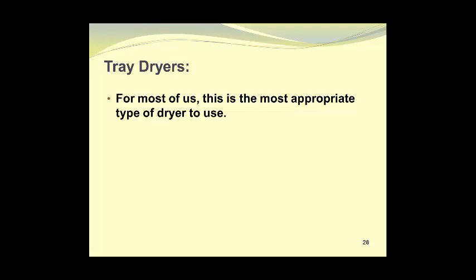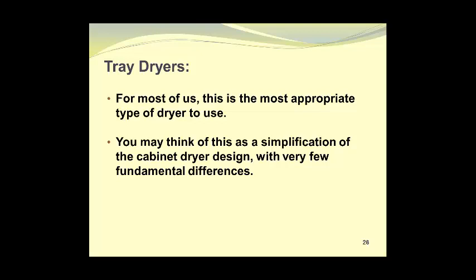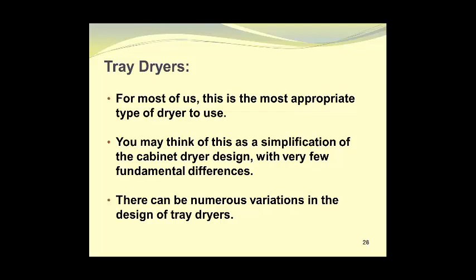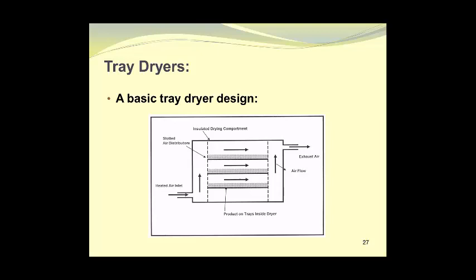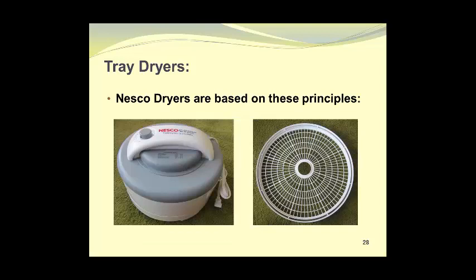Tray dryers are the most appropriate type of dryer for most of us to use. You may think of this as a simplification of the cabinet dryer design with very few fundamental differences. There can be numerous variations in the design of tray dryers. Here we see a basic tray dryer design. Heated air enters through an inlet at the bottom left-hand corner. The slotted air distributors ensure uniform air distribution across the three trays of material being dried. The air then exits through the exhaust stack at the opposite end of the dryer.